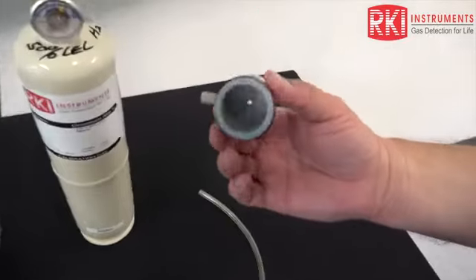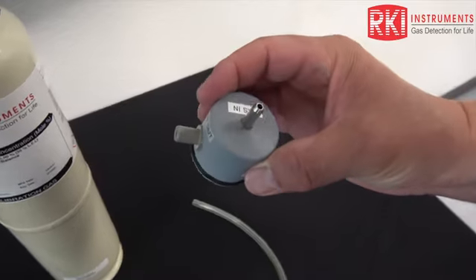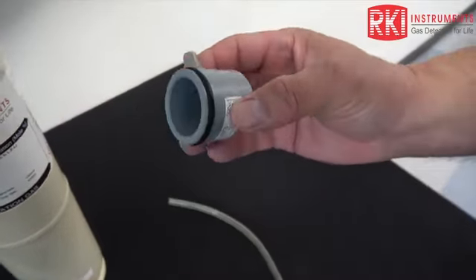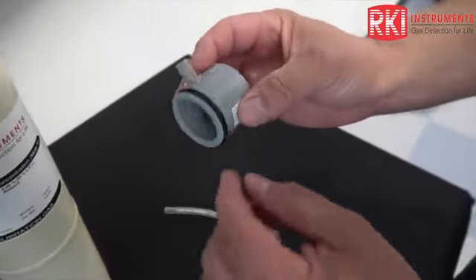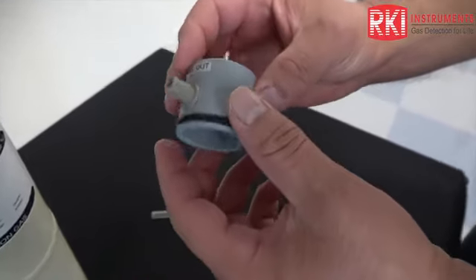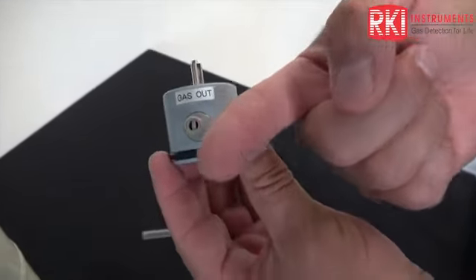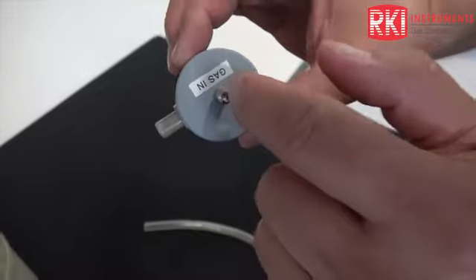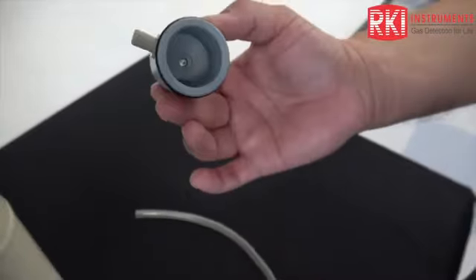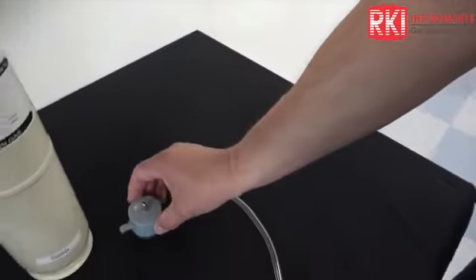And this is a calibration cup. This is a proprietary cup that is designed for use with the SD1 series. So it's got an O-ring to give you a good seal. You've got the gas out port, and then also a gas in port. So it quickly identifies how to connect your hose and where you should connect it.